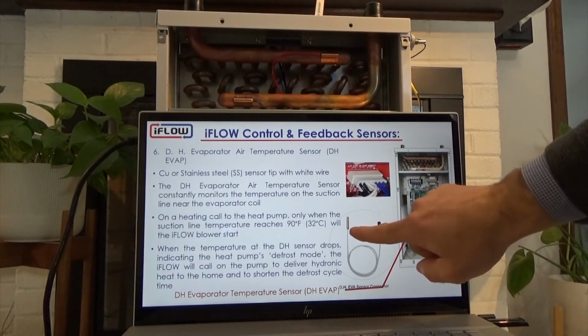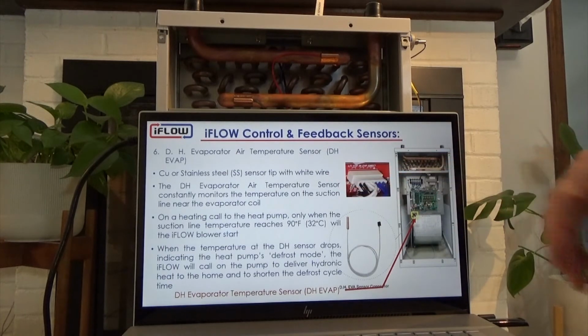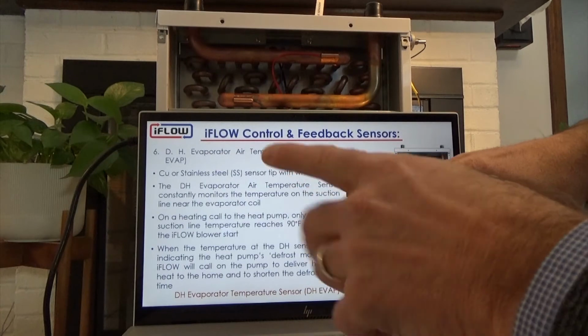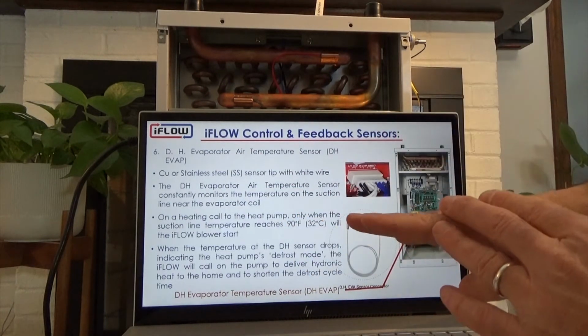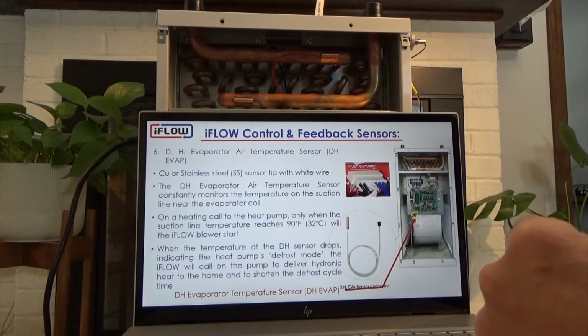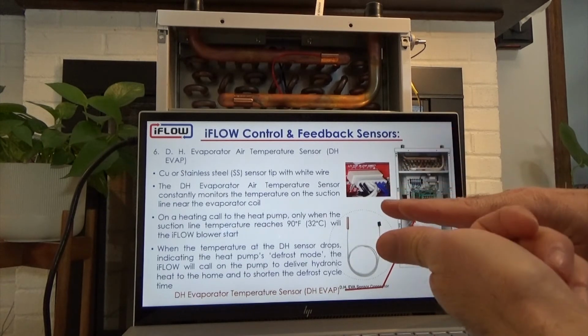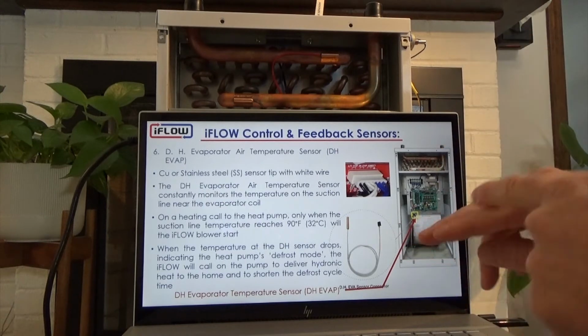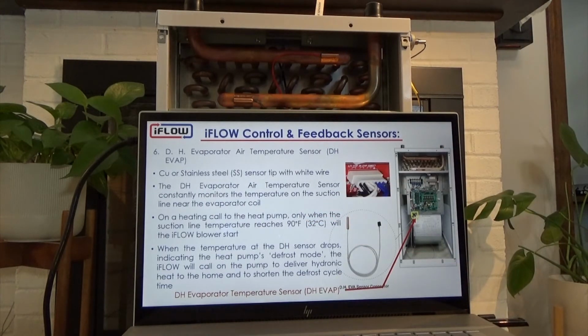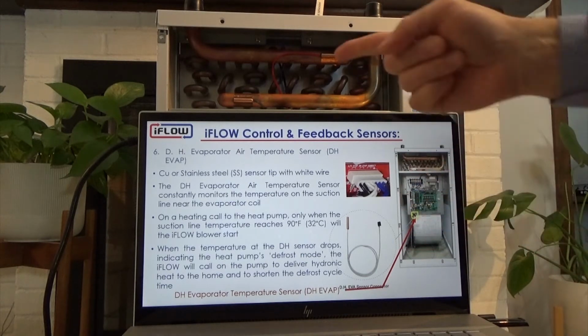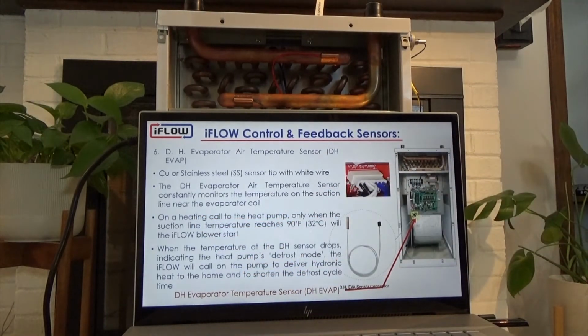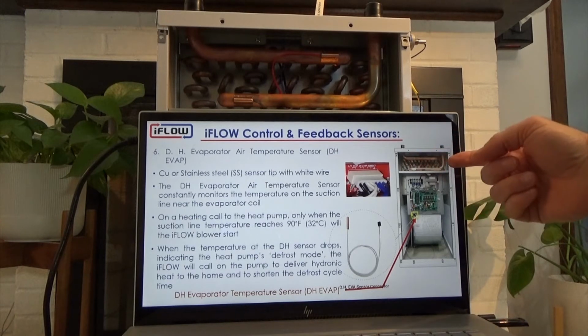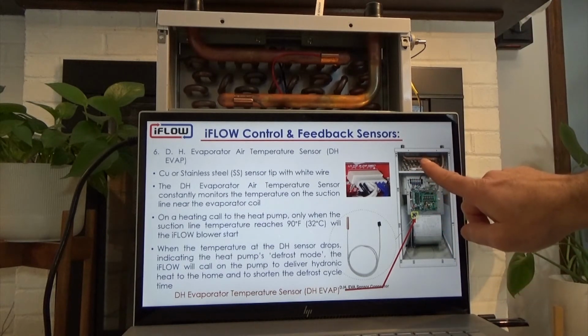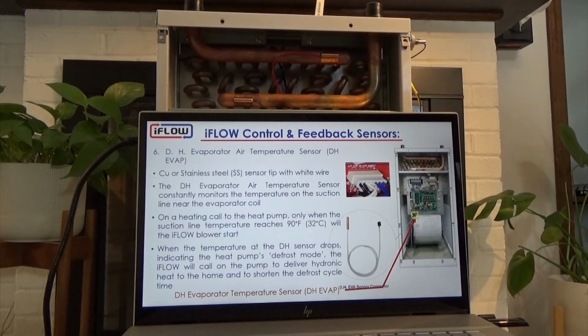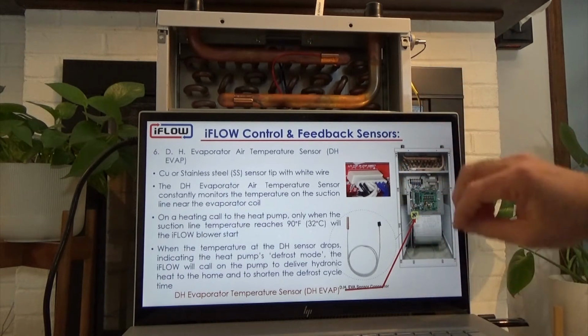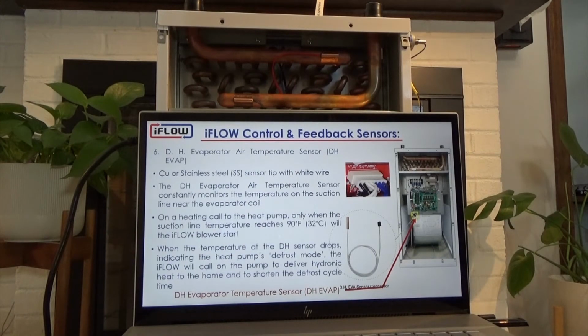The other thing that the DH evaporator sensor does when it's measuring the temperature on the line: you can imagine, we're supplying heat out, let's say above 90 degrees, so maybe 100 or 110 degrees, into the evaporator coil, and then all of a sudden the heat pump has to go into defrost mode. Well, it's going to switch to AC, so the reversing valve is going to change. The temperature on that line will change immediately, and that's when we know that we're going into defrost mode. When the heat pump goes into defrost mode, as we detect by the evaporator temperature sensor, then we will bring on the hydronic pump, bring hot water into the coil and bring the blower on so that we can deliver heat into the house while the heat pump is in defrost mode. That heat is also going to go into the evaporator, and we're going to be able to shorten the defrost cycle time.